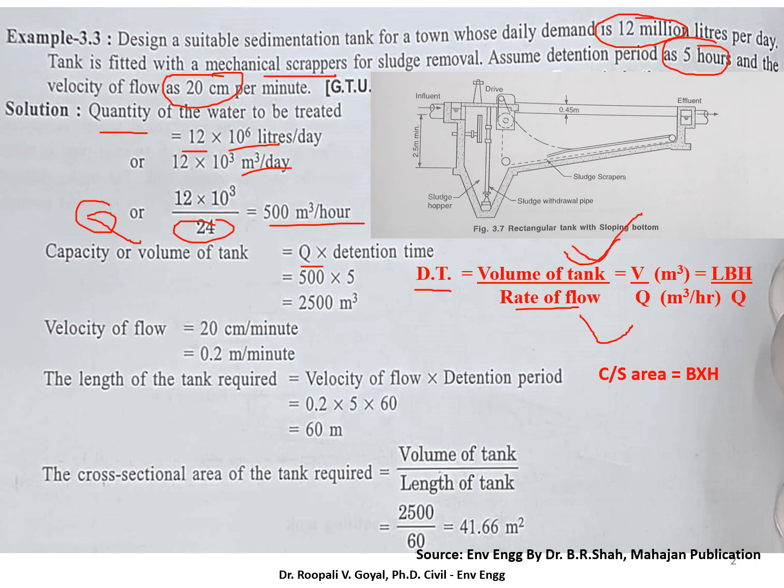So volume of tank is Q into detention time. So Q is in meter cube per hour, 5 hours is your detention time. So you will get 2500 meter cube as volume. Now we have the volume and we have horizontal velocity.